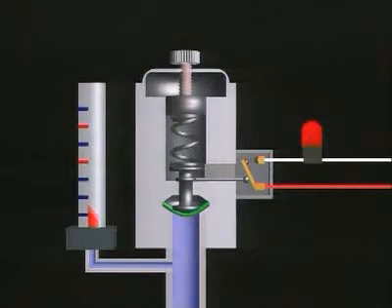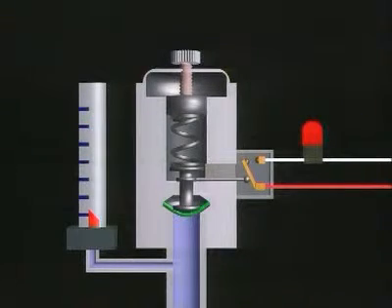If the pressure drops, the switch automatically opens again at a certain pressure. The difference between the switch on point and the switch off point is the hysteresis of the pressure switch. This varies according to the pressure range. The hysteresis is caused by the frictional resistance in the components of the switch.